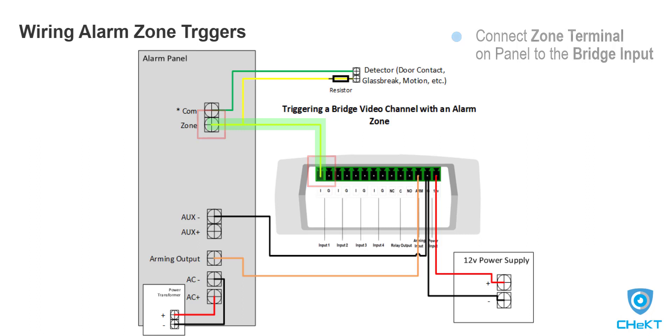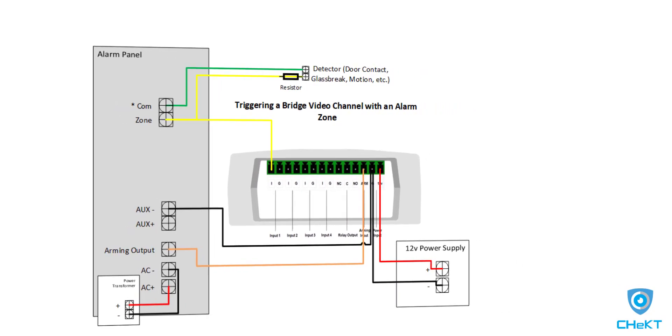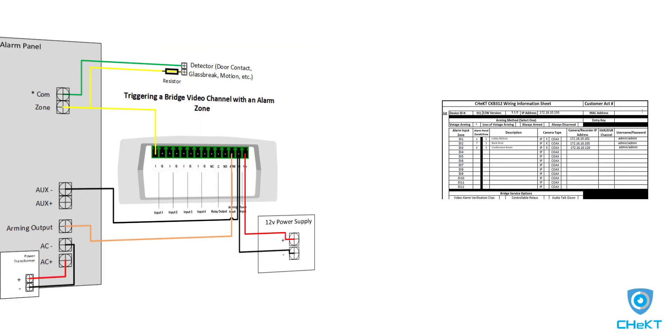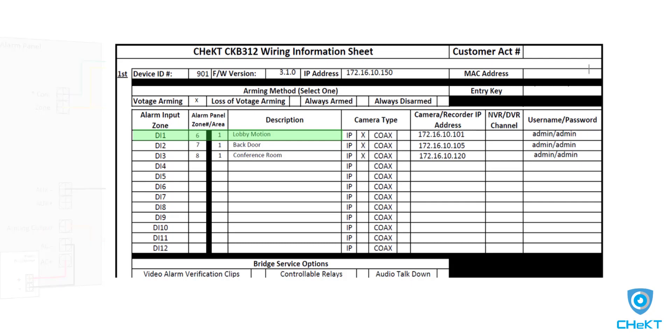Once cameras are added, the trigger wire will create a video alarm on the video channel associated with the digital input. Each of the bridge digital inputs are internally associated with a video channel. For example, digital input 1 is associated with video channel 1, digital input 2 is associated with video channel 2, and so on. By using a notepad or the CHeKT bridge wiring information sheet, document the alarm panel zone you are wiring into which digital input.